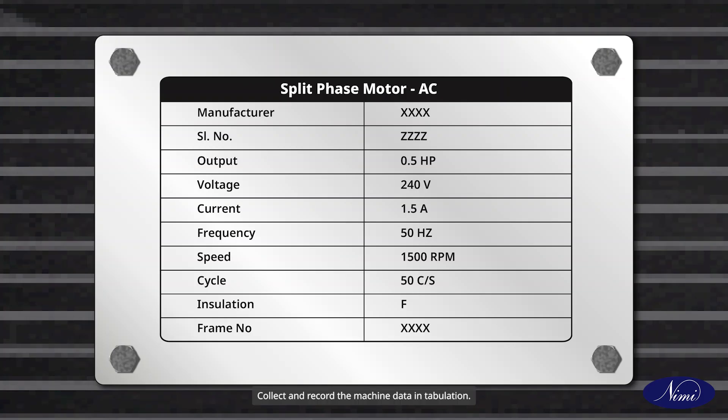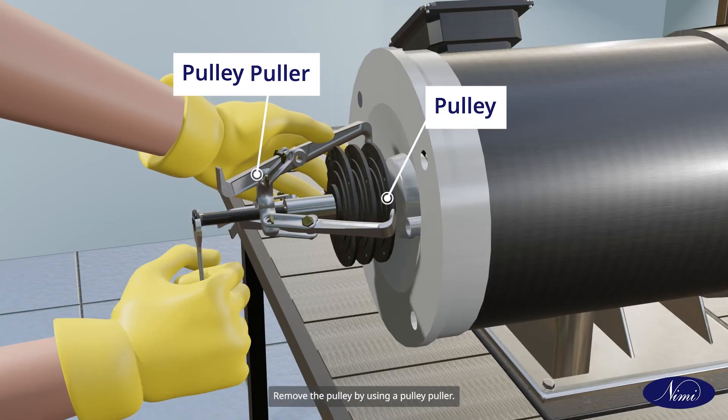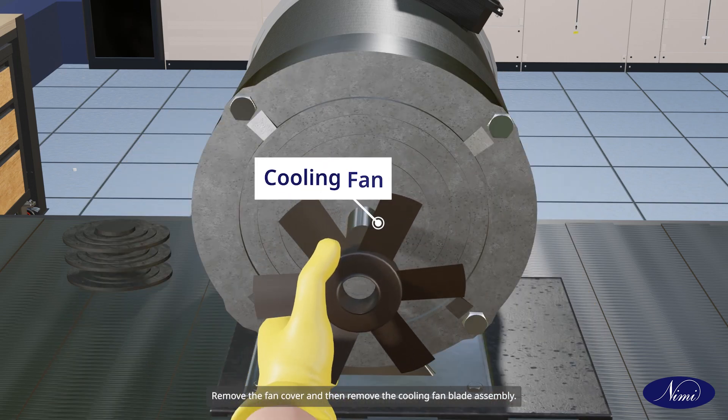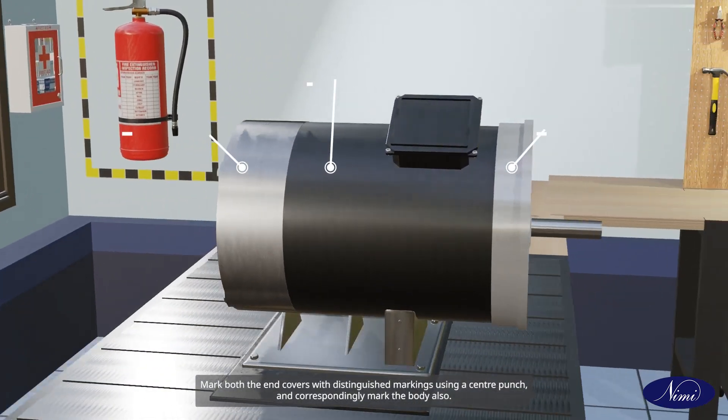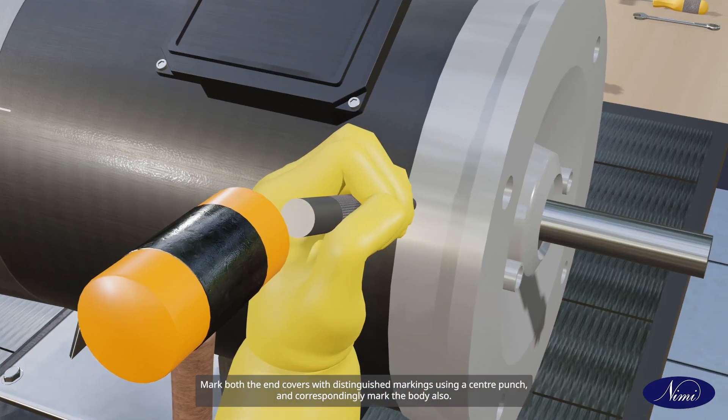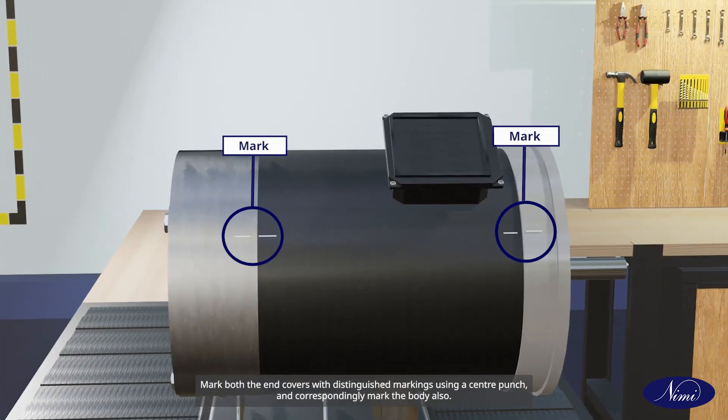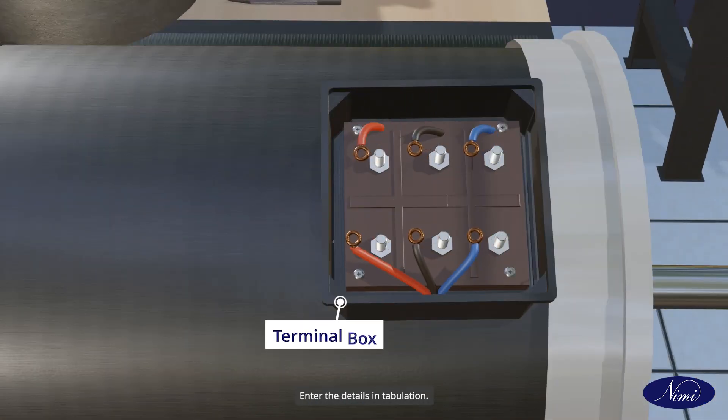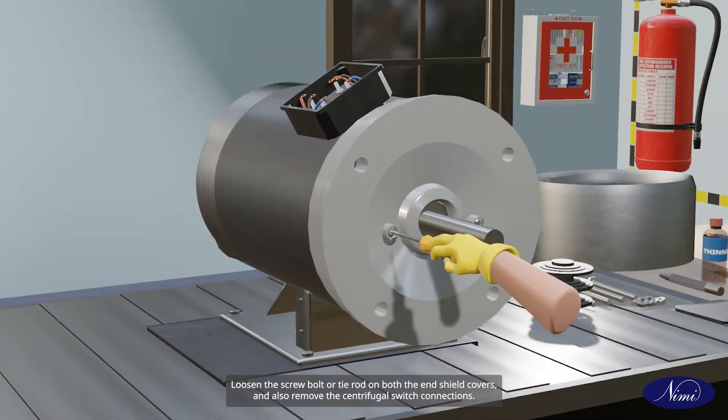Remove the pulley by using a pulley puller, remove the fan cover and then remove the cooling fan blade assembly. Mark both the end covers with distinguished markings using a center punch and correspondingly mark the body also. Mark and remove the connection leads from the terminal box and enter the details in tabulation.